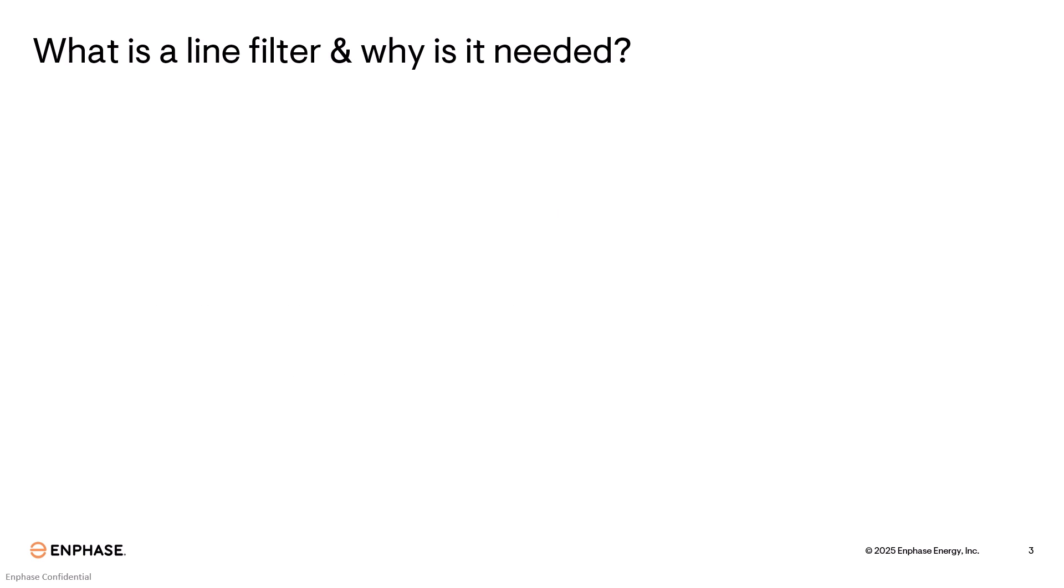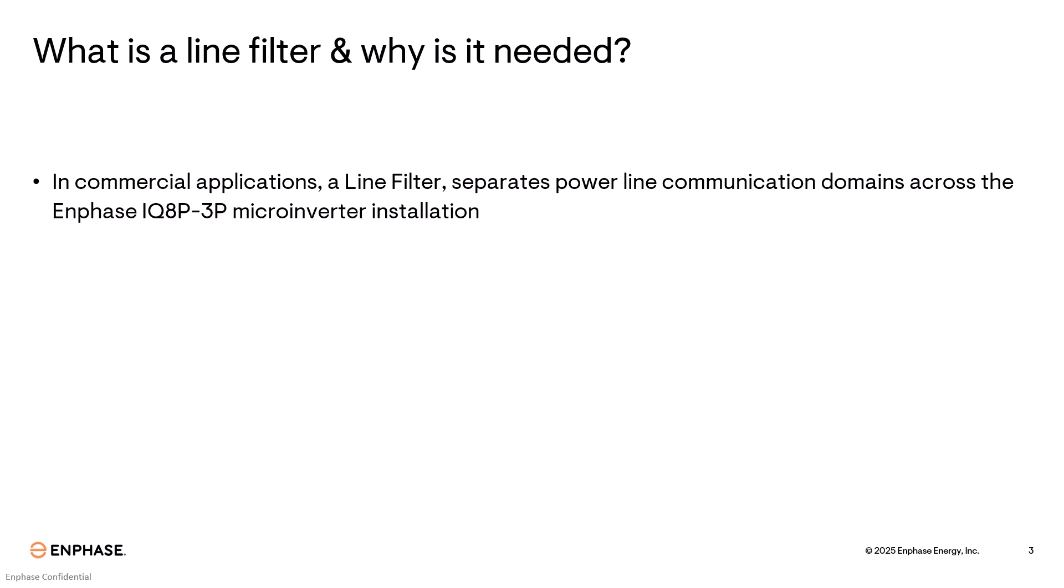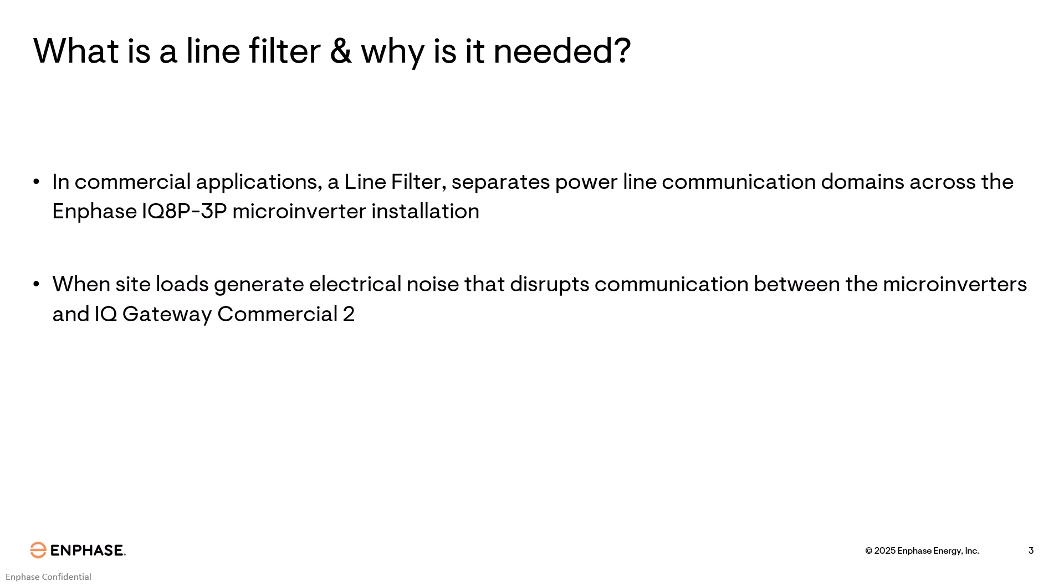What is a line filter and why is it needed? In commercial applications, a line filter separates power line communication domains across the Enphase IQ8P-3P microinverter installation. A line filter might be needed when site loads generate electrical noise that disrupts communication between the microinverters and the IQ gateway commercial two. Some examples of site loads that generate excess electrical noise might be large electrical motors or medical equipment.